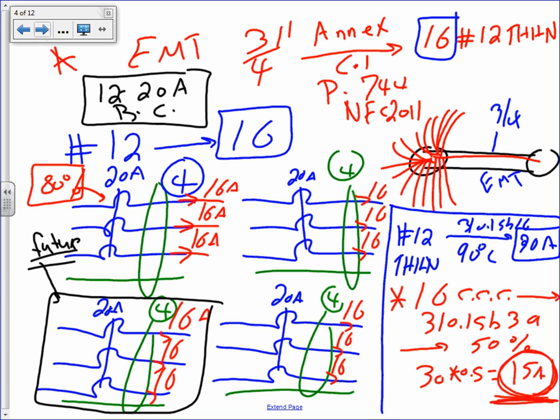Okay? Now, here's what I suggest. Not suggest. The maximum circuits that you can carry inside this conduit. Let me explain. So you have a 20 amp circuit for continuous. Everybody, why do you think I'm pulling 16 out of a 20 amp circuit? Continuous, you can't take more than 80% of the rating of the circuit breaker.